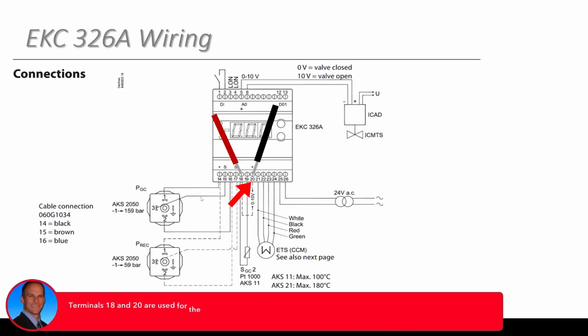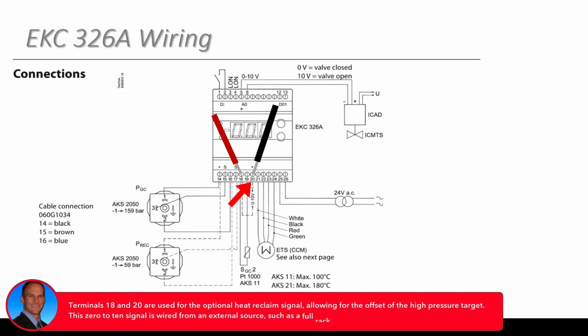Yep. For sure. 18 and 20 here. This is the heat reclaim signal that I had mentioned a few minutes ago. So this isn't mandatory usage or input. This would be optional if we have heat reclaim and if we want to offset the high pressure target. So 18 and 20 is where we would wire that 0 to 10 signal from, which will be coming from something external, whether it's, again, the full rack controller that's being used or something else. That's the two terminals we would wire to for that signal.